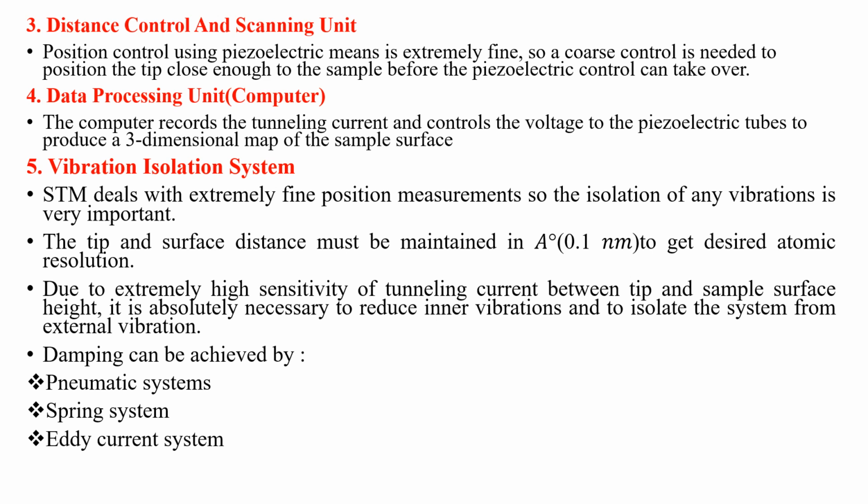As the STM deals with extremely fine position measurement, it should be free from vibrations, and the distance between the tip and surface is maintained around 0.1 nanometer, which is very small, to get the desired atomic resolution. Due to this extremely high sensitivity, it is absolutely necessary to reduce vibration and to isolate the system from external vibrations, which can be done by using damping. Damping can be achieved by either of three systems: a pneumatic system, a spring system, or an eddy current system.